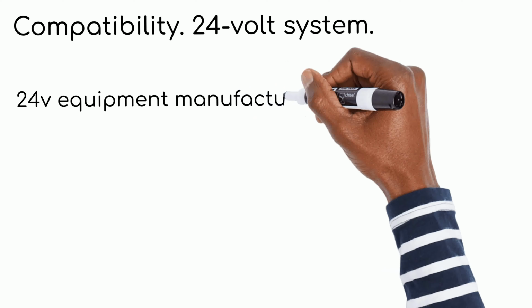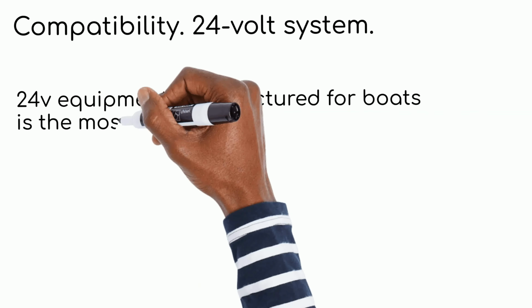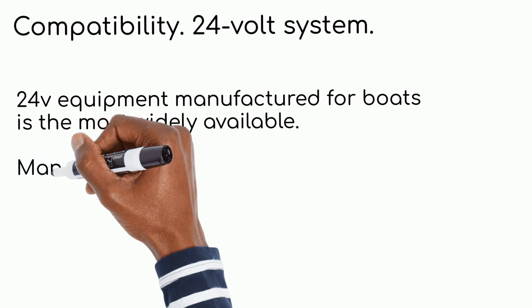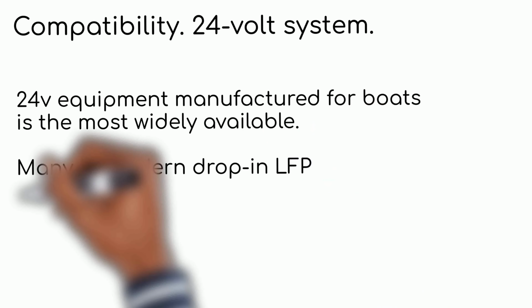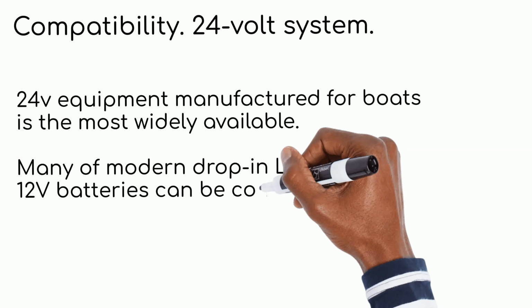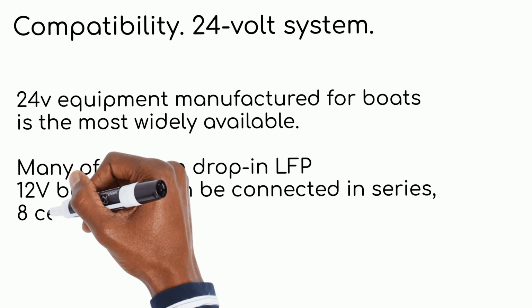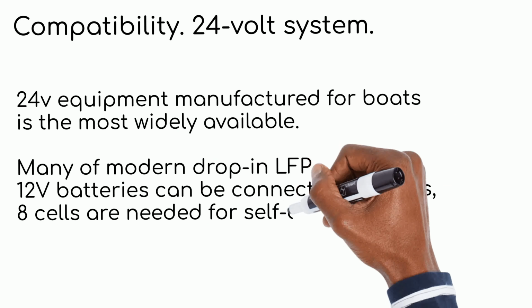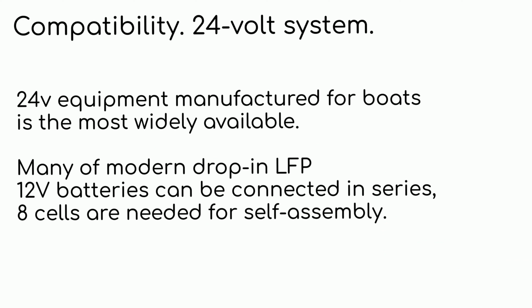24-volt equipment manufactured for boats is also widely available for sale. Lamps, water makers, toilets, winches, pumps, and all the rest, everything is available for a 24-volt system. High-consumption equipment is also available. Serial connection of drop-in LiFePO batteries for organizing 24-volt is not available for all manufactured batteries, but finding the right one is not a big problem. For the self-assembly of LiFePO batteries, we need 8 cells.